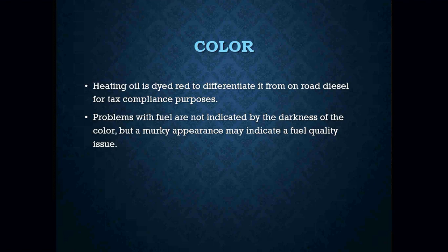Okay, the color of your heating oil is nothing more than a dye. That dye is added to your heating oil to differentiate it from your on-road diesel fuel, simply for tax compliance purposes. Problems with fuel are not necessarily indicated by the color of it, but if you have oil that has a murky appearance to it, that may be an indication of a fuel quality issue. It could have some water or something in there.